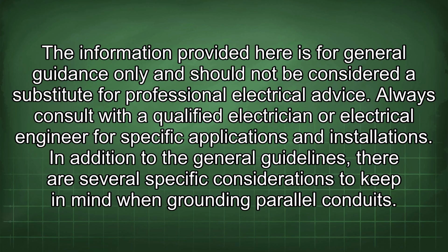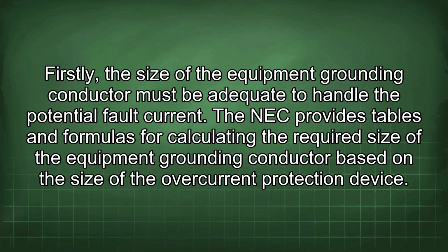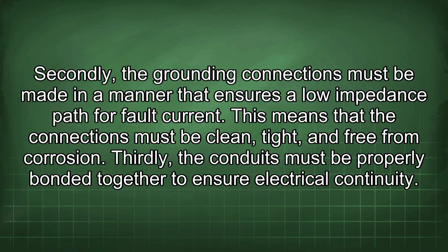In addition to the general guidelines, there are several specific considerations to keep in mind when grounding parallel conduits. Firstly, the size of the equipment grounding conductor must be adequate to handle the potential fault current. The NEC provides tables and formulas for calculating the required size of the equipment grounding conductor based on the size of the overcurrent protection device. Secondly, the grounding connections must be made in a manner that ensures a low impedance path for fault current. This means that the connections must be clean, tight, and free from corrosion.